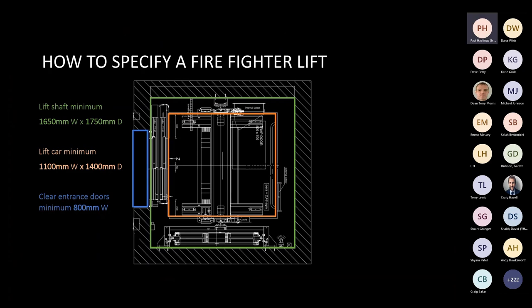A firefighting lift can be a minimum of 8 persons, with 13 persons being most common. Lift shaft sizes are 1650mm wide by 1750mm deep, with a minimum car size of 1100mm by 1400mm and a minimum entrance of 800mm wide. This would fully comply with EN 81-72.